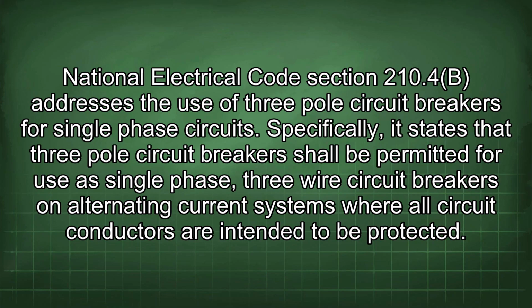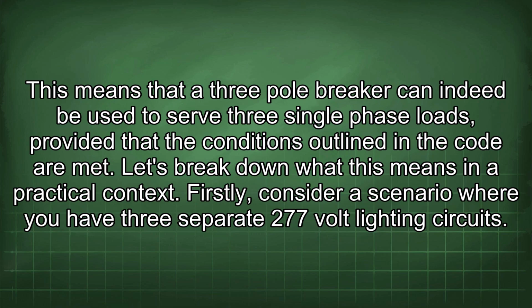National Electrical Code Section 210.4(B) addresses the use of three-pole circuit breakers for single-phase circuits. Specifically, it states that three-pole circuit breakers shall be permitted for use as single-phase, three-wire circuit breakers on alternating current systems where all circuit conductors are intended to be protected. This means that a three-pole breaker can indeed be used to serve three single-phase loads, provided that the conditions outlined in the code are met. Let's break down what this means in a practical context.